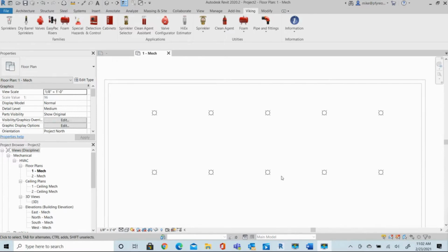The default Viking families only use the NFPA 170 recommended symbols, and NFPA does not take into consideration how these are really applied in real shop drawing situations. So we need to make a simple adjustment and apply our own custom symbol to this plan. Many companies have their own set of custom symbols already, and we've supplied you with a tool so that you can recreate those and incorporate those into your plan.